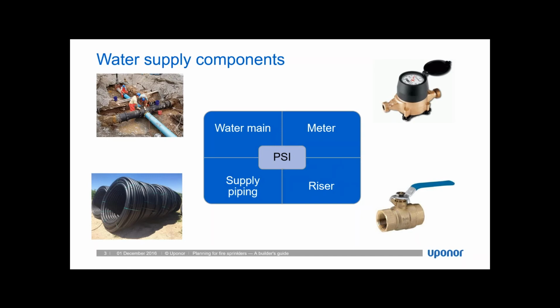After the ball valve, the system riser will then have a T that's going to go off to your water heater, a possible secondary T that's going to go to the cold water fixtures in the home if we're dealing with a standalone sprinkler system. Otherwise, if we are not, and we are dealing with a multi-purpose sprinkler system, you may have some additional lines coming off of your riser to feed any cold water fixtures that you would like to remain independent of that sprinkler system. Otherwise, the remainder of the pipe will supply both the sprinklers and the cold water fixtures throughout the home. These water supply components shown here are all that is required for the most simplistic residential fire sprinkler system, which is a multi-purpose system, where that piping throughout the home is supplying the sprinklers and the water fixtures. I will also go over what's required in many areas when standalone sprinkler systems are selected.